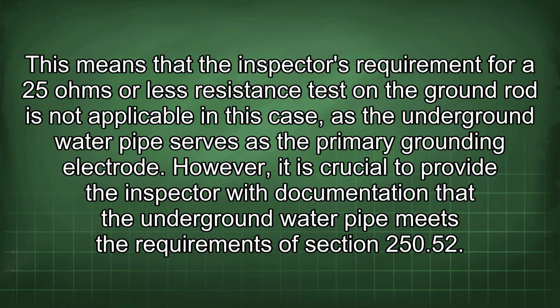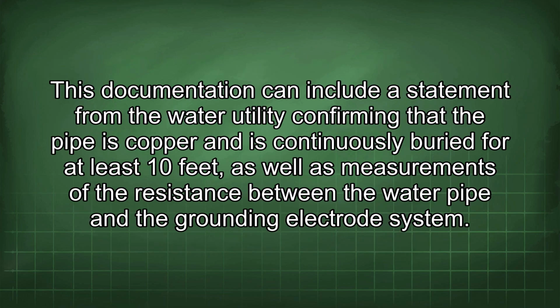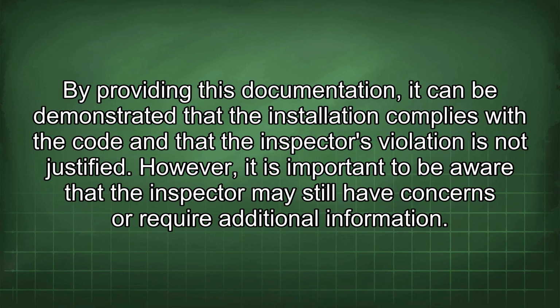However, it is crucial to provide the inspector with documentation that the underground water pipe meets the requirements of section 250.52. This documentation can include a statement from the water utility confirming that the pipe is copper and is continuously buried for at least 10 feet, as well as measurements of the resistance between the water pipe and the grounding electrode system. By providing this documentation, it can be demonstrated that the installation complies with the code and that the inspector's violation is not justified.